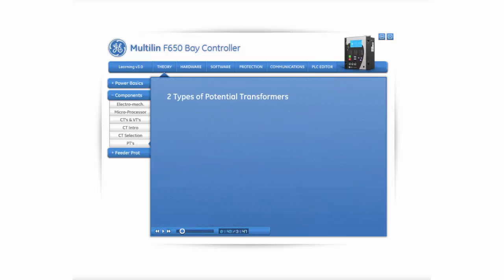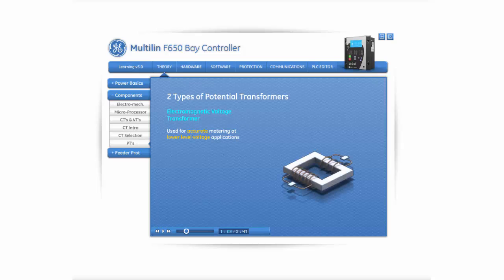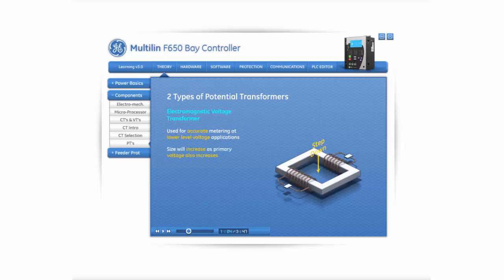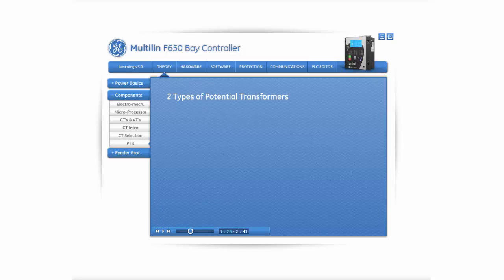There are 2 different types of potential transformers used today: the electromagnetic voltage transformer and the capacitive voltage transformer. Electromagnetic voltage transformers are usually used when accurate metering needs to be performed for lower voltage applications. Capacitive voltage transformers are commonly used in high voltage transmission line applications where the voltage is higher than 66 kilovolts. Electromagnetic voltage transformers have dense winding drops designed to accurately scale down the voltage and make sure the ratio is consistent for all variations in the input voltage. Due to the small amount of voltage drops per winding, the electromagnetic voltage transformers will increase in size as the rated primary voltage also increases. Likewise, the cost of electromagnetic voltage transformers tends to increase at a disproportionate rate to the primary voltage rating.